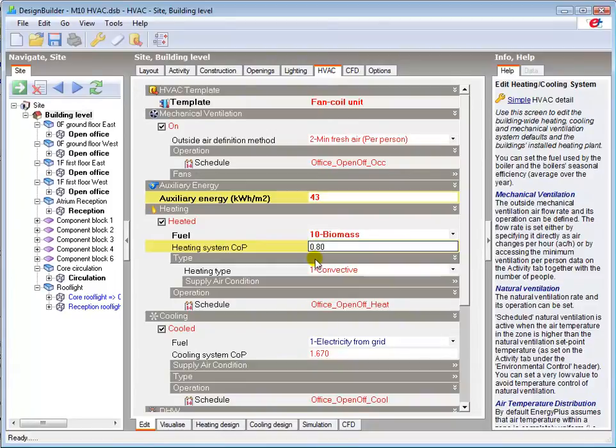There is an option to change the heating type to radiant or convective, but you should be aware that selecting this will slow simulations down significantly, and so it should only be selected when the radiant fraction of the heating system really must be modelled, for example for heated floors. For typical hot water radiators and baseboard heaters with radiant heating fractions of 0.2 or less, you'll normally be better off using the standard 100% convective heating system and accepting a small inaccuracy.